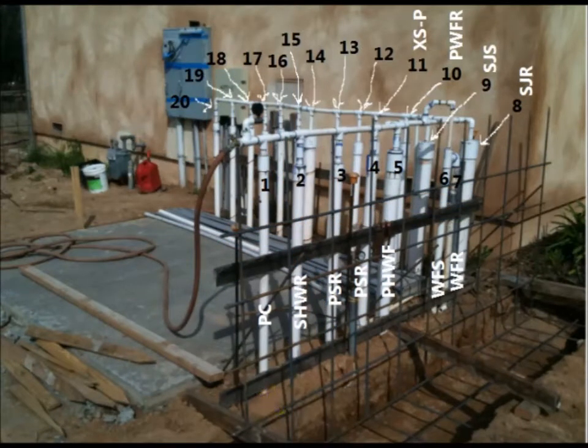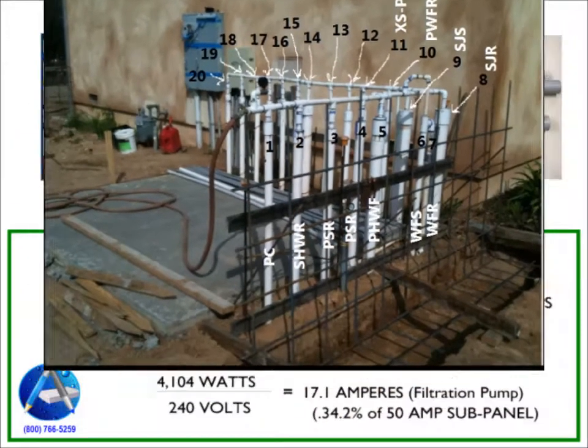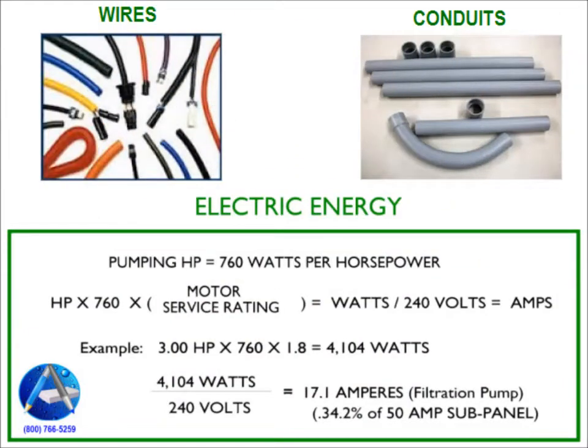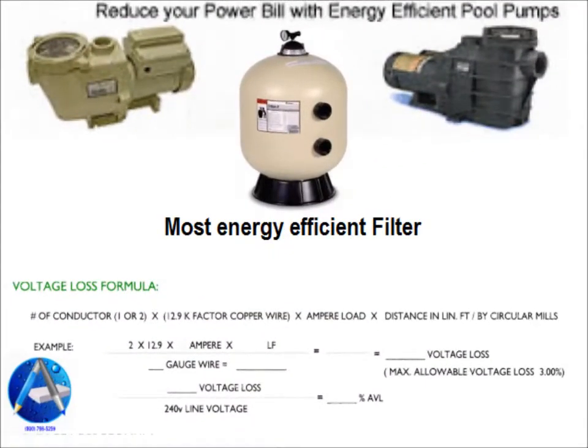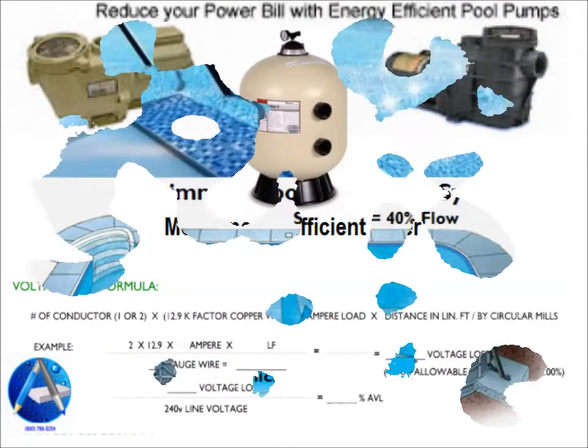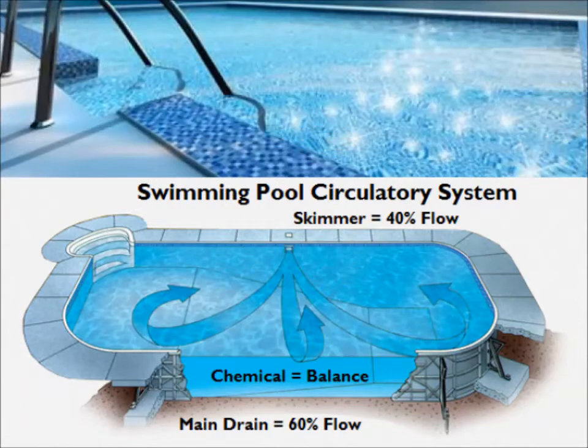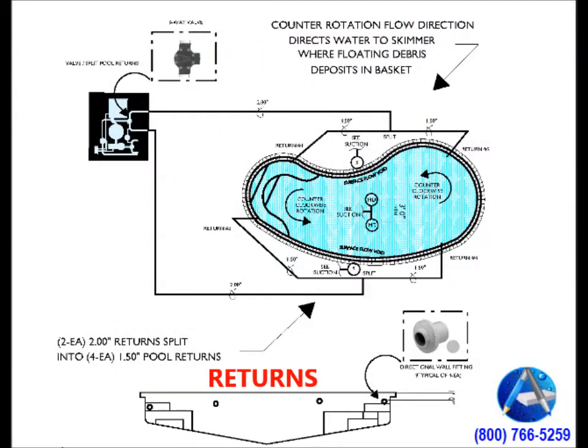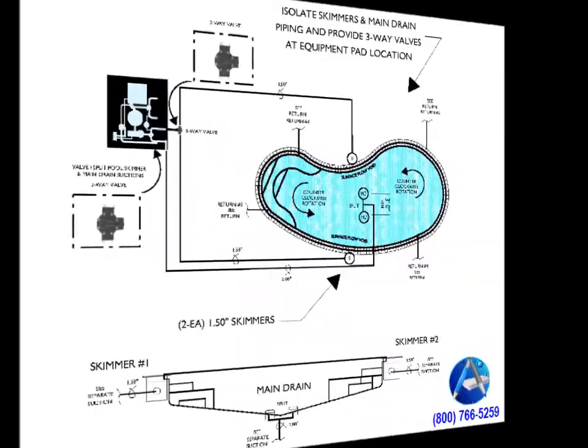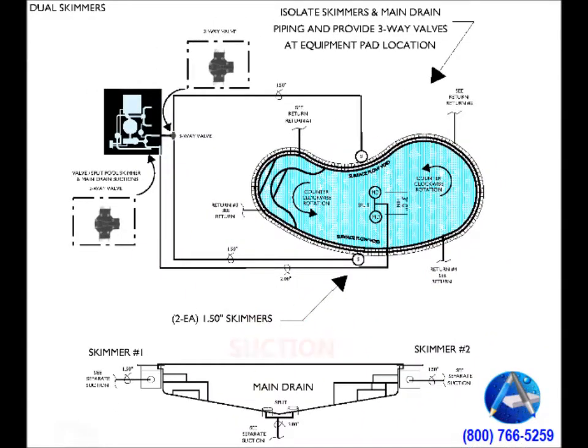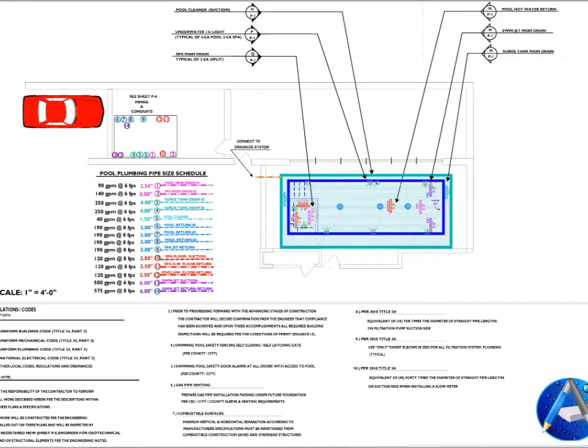Our level of planning calls out the plumbing pipe sizes that meet the Title 24 energy-efficient flow characteristics, as well as calling out the conduit and wire gauges that will meet the National Electric Code allowable voltage losses along a given run's distance. Our plans anticipate and call out what will be necessary in accomplishing a less expensive pool to operate and a grief-free pool in which to maintain.